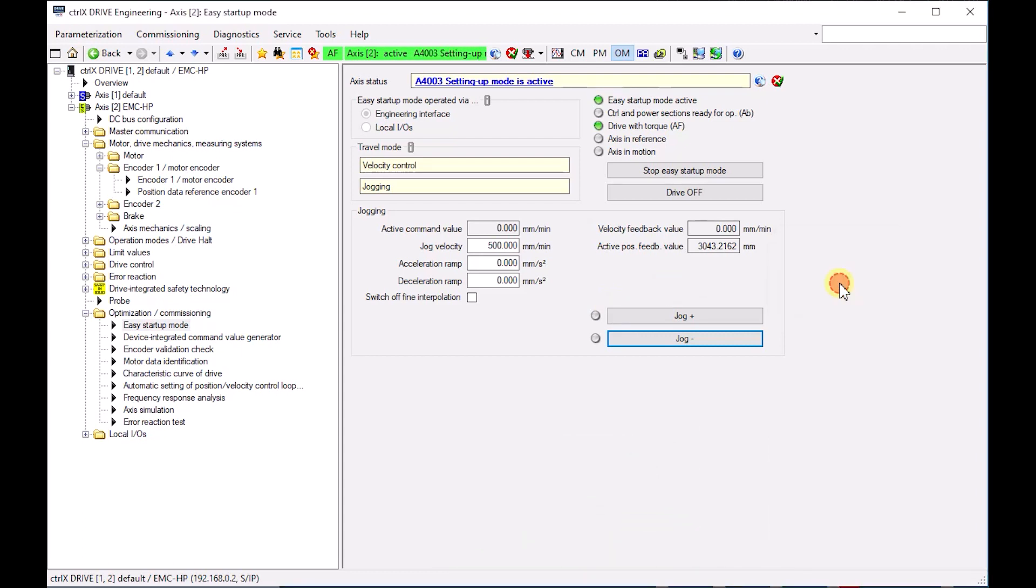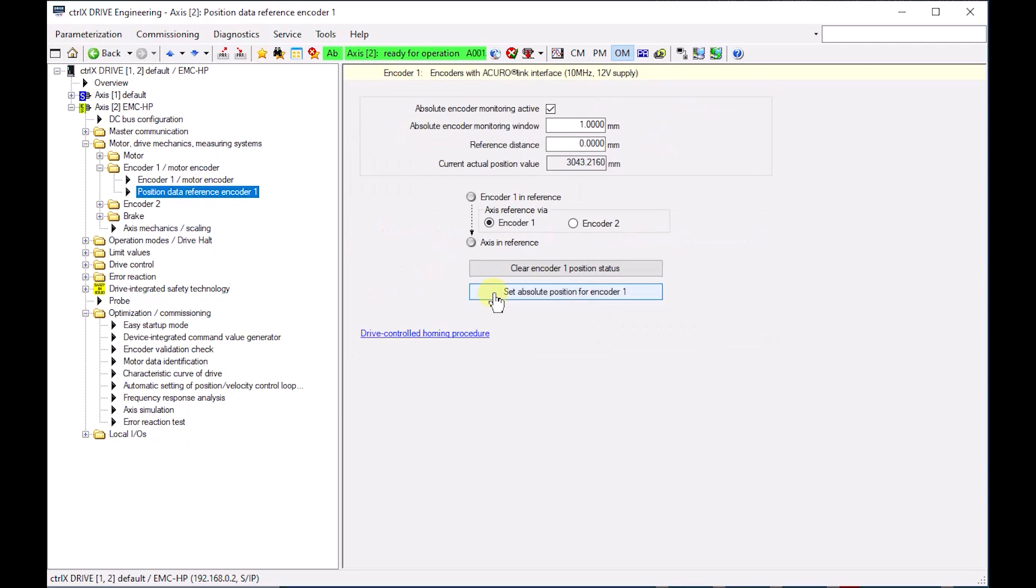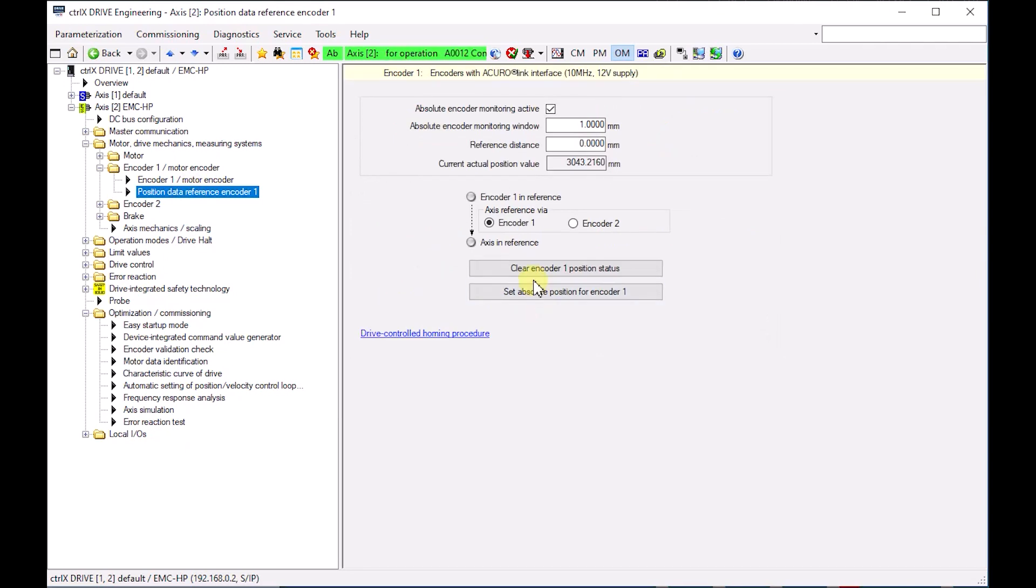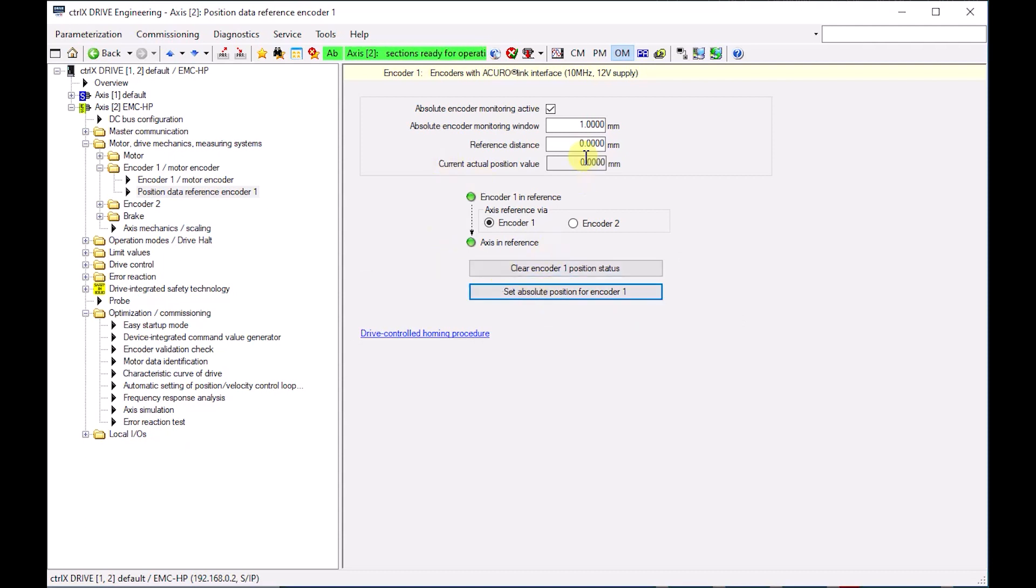Now, to set the absolute position, move to position data reference encoder 1, click on set absolute position for encoder 1, and now the current physical position of the actuator is set as the zero point.